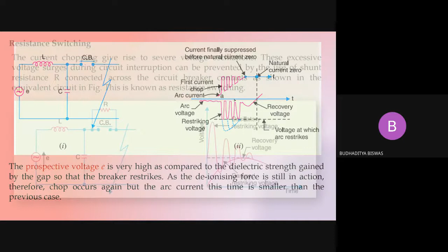Now why is this required here? First of all, you see the current chopping gives rise to severe voltage oscillation. This excessive voltage surge during the current interruption can be prevented by using a shunt resistance R connected across the circuit breaker contacts. So here you see, across the circuit breaker contacts, one resistance is there. This resistance is making a bridge around the circuit breaker contacts as shown in the figure and the equivalent circuit. This is known as resistance switching.